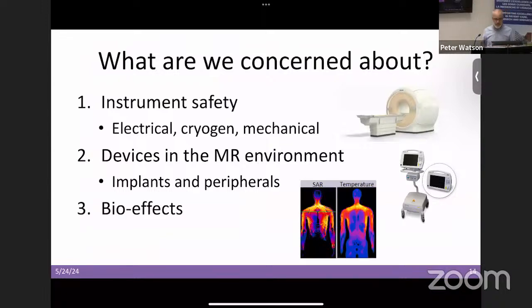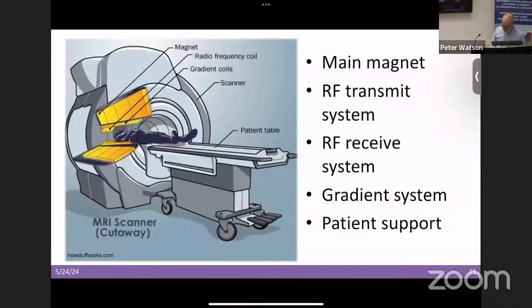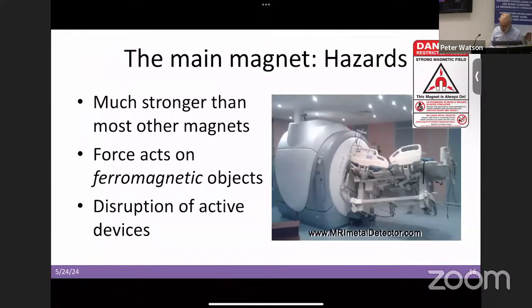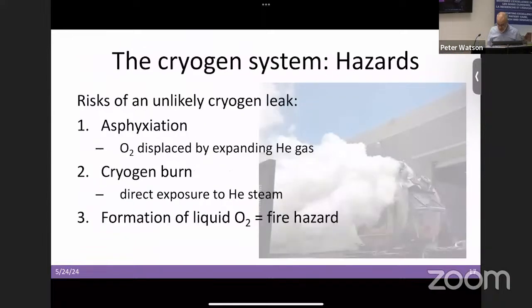And last but not least, bioeffects. So even the plain Jane human beings who have no implants and need no peripherals, there are some possible bioeffects. These effects arise from the various subcomponents and fields they generate in the MRI scanner, which you may or may not already be familiar with, but there are these three field generators: the main magnet, the RF field transmit system, and the gradient system. The hazards related to them are, of course, forces on ferromagnetic objects, which are on all the time. The cryogen system, the presence of liquid helium inside the MRI scanner, which in normal times you should never see. But should there be either a system failure or an intentional release of the cryogen, it can lead to some potential hazards for people in the area.